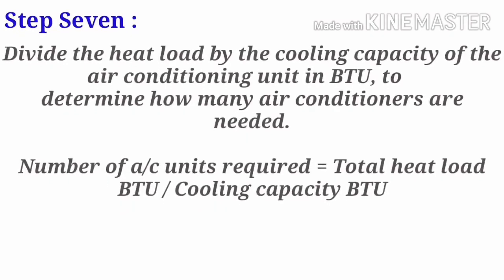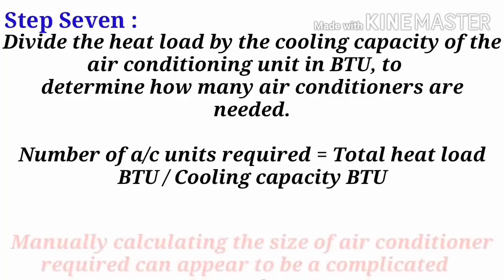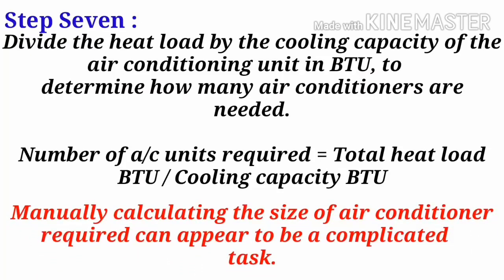Step 7: Divide the heat load by the cooling capacity of the air conditioning unit in BTU to determine how many air conditioners are needed. Number of AC units required equals Total Heat Load (BTU) divided by Cooling Capacity (BTU). Manually calculating the size of air conditioner required can appear to be a complicated task, but in this way you choose the required cooling capacity unit by calculating the heat load.